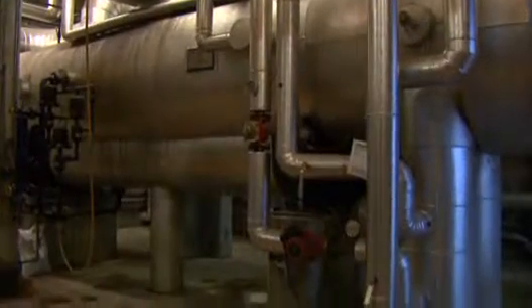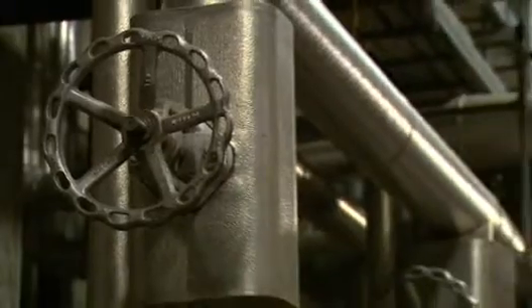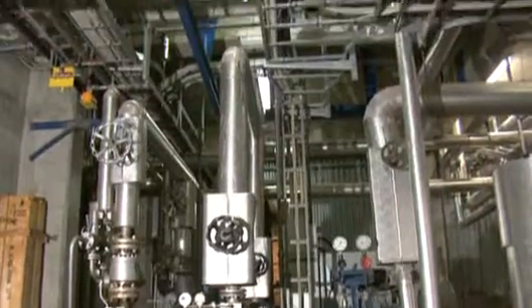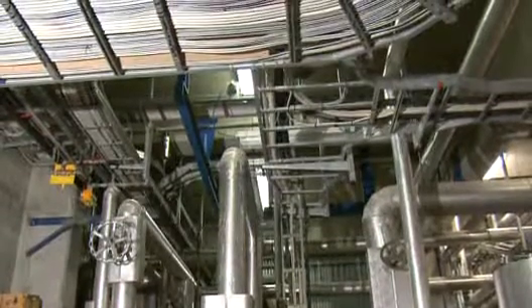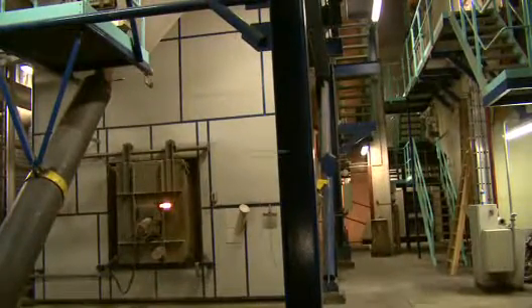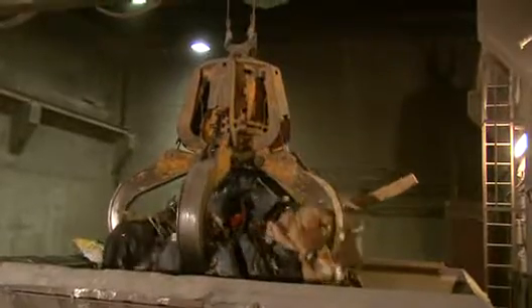When the steam has delivered the energy to the electricity production in the turbine, it is channeled to the condenser. Here the steam is warming up the circulating heating water. Thereby the steam gives up so much heat that it turns into water again, and this recovered water is pumped back to the kettle system. In all, the kettle contains 30,000 litres of water, and it only takes 1.5 hours to transform this amount of water into 30 tons of steam.